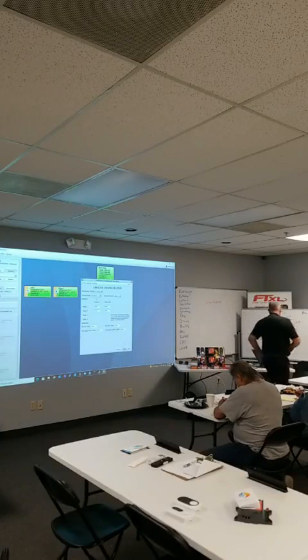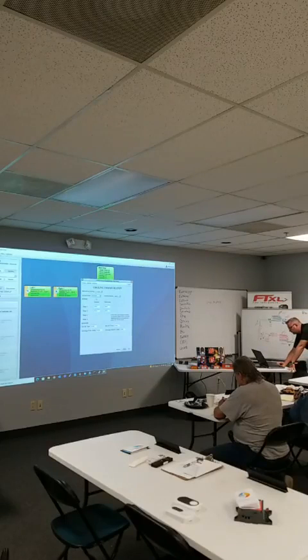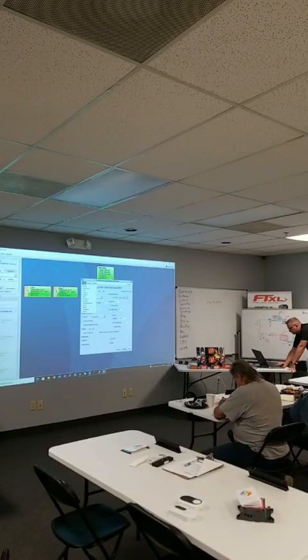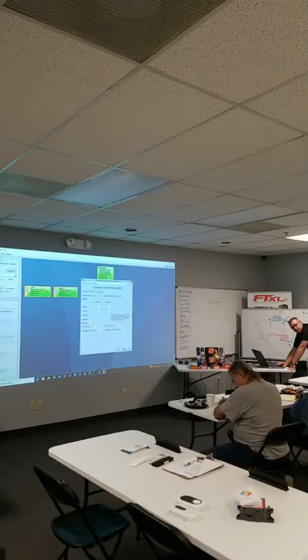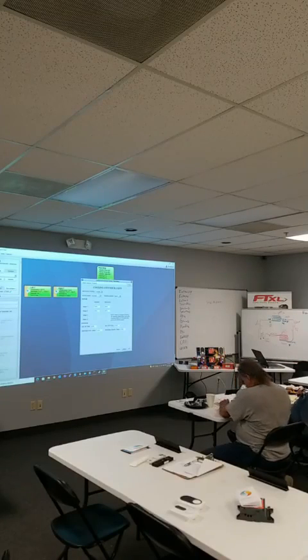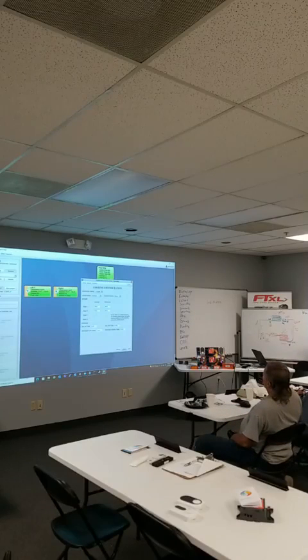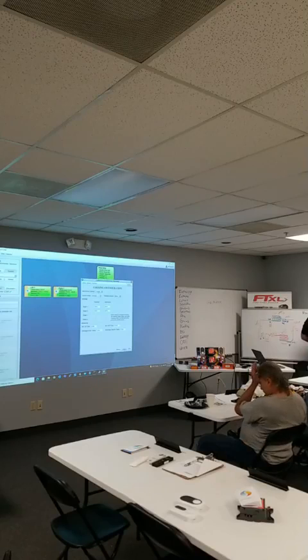We can do 2 different units? I think we can do 2 heat. I know that was something we had kind of broached, but never really focused on: trying to run a reheat, with air conditioning to dehumidify. Preheat, then cool. You would wait that second stage longer to give you more dehumidification. There are some new applications for this coming out. I can't tell you when, because I'm not sure, but I know it wasn't there. If you're doing hot gas, we don't have modulating hot gas reheat. It's open or closed hot gas reheat.